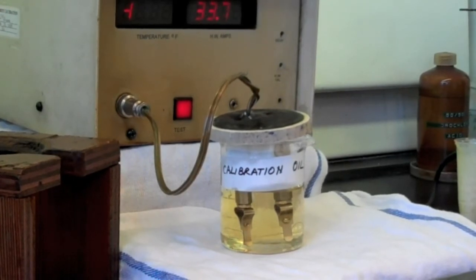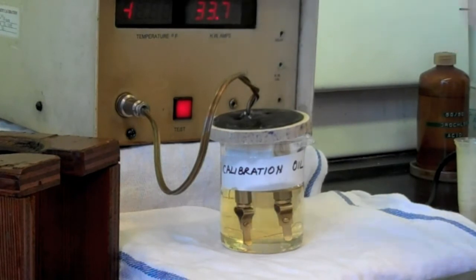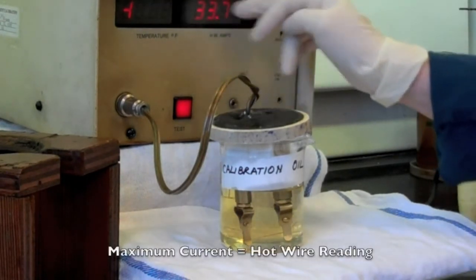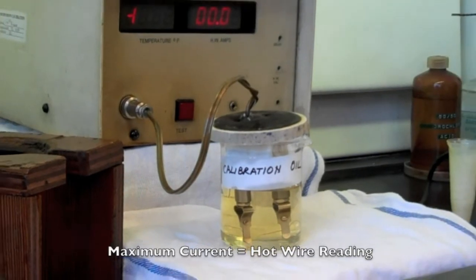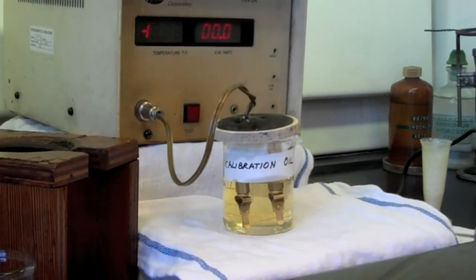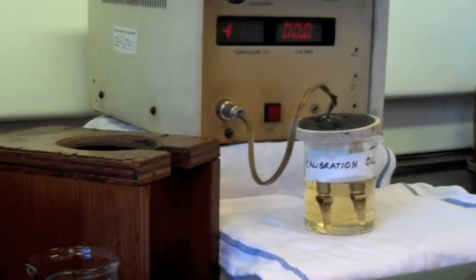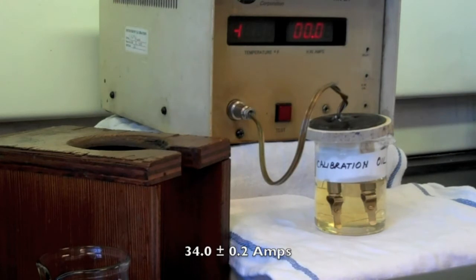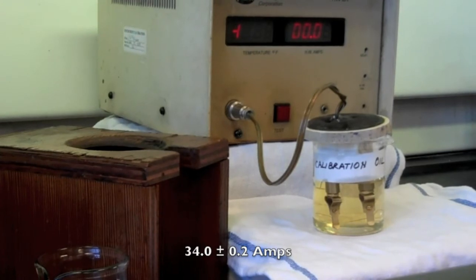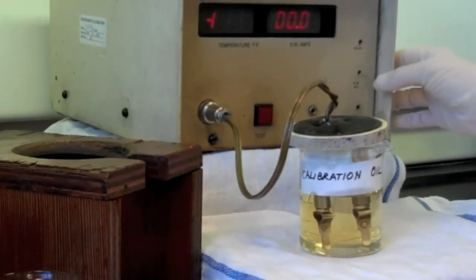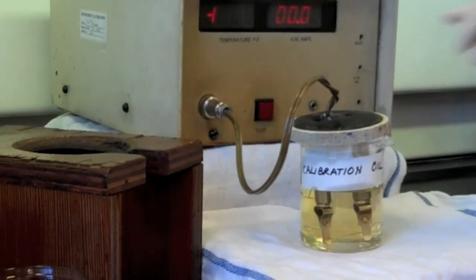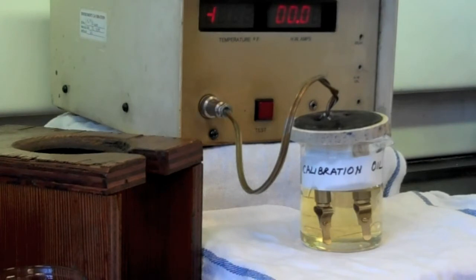This maximum current that the wire can take before burning out is locked on the display, and it's taken as the hot wire reading. 3 such determinations are taken, and the average value is considered to be the quench speed of the oil. For the calibration oil, the value that we are expecting is 34 plus or minus 0.2 amps. If that's not the case, the apparatus has a calibration knob here that can be adjusted, and the test is repeated again until the value falls within the spec.